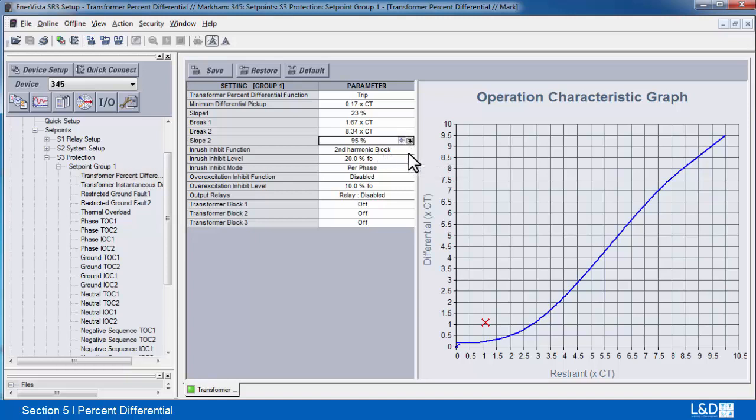And for the other settings, for the inrush inhibit, we can select the second harmonic and use 20% as the default. For the inhibit mode, we have per phase, 2 out of 3, and average. For the overexcitation inhibit, we can set this to use the fifth harmonic, and we're going to use 10% of the levels.